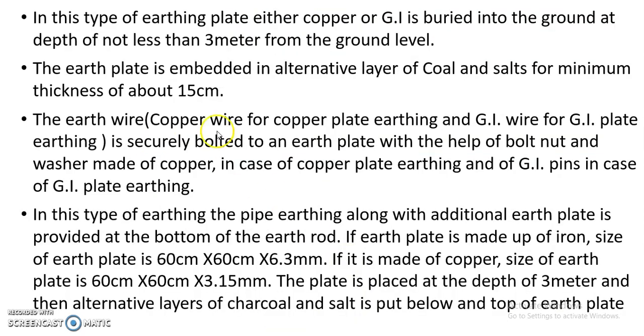So in this type of earthing, the plate, either copper or GI, that is galvanized iron, is buried into the ground at depth not less than 3 meters from the ground level. The earth plate is embedded in an alternative layer of coal and salt for minimum thickness about 15 centimeter. Then the next point is the earth wire, that is copper wire for copper plate earthing and GI wire for GI plate earthing, is securely bolted to an earth plate with the help of bolt and nut and washer, which is made up of copper in case of copper plate earthing, and it is made up of GI pins in case of GI plate earthing.